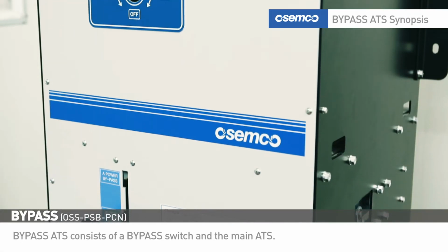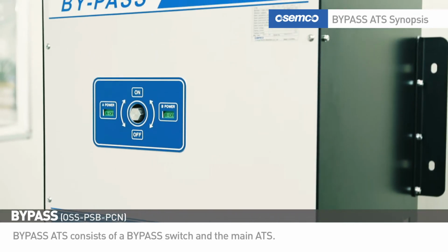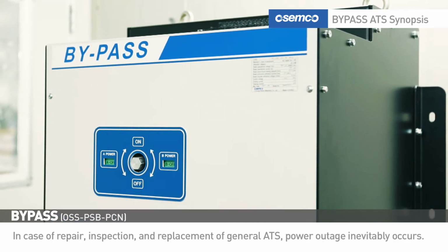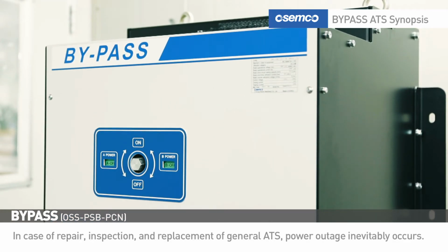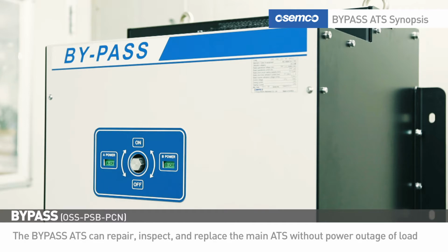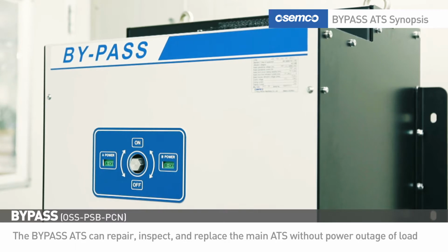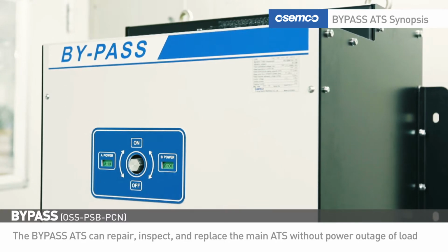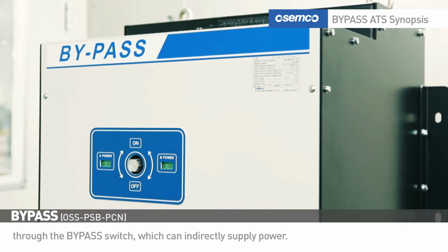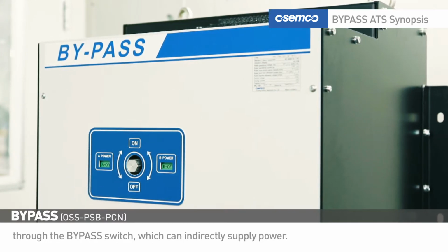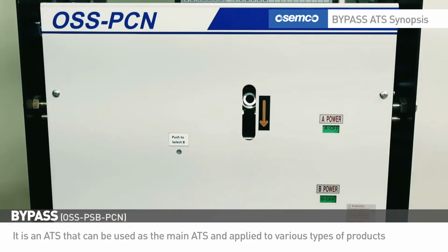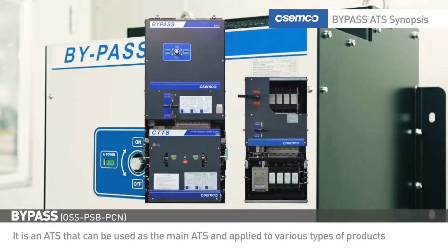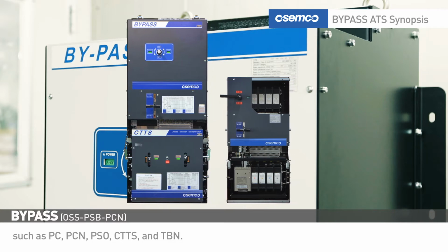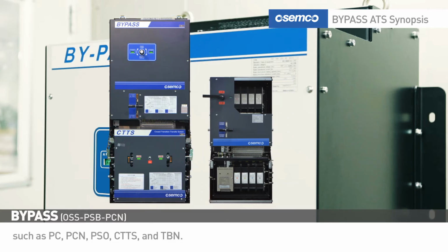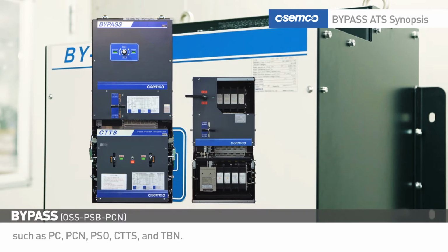Bypass ATS consists of a bypass switch and the main ATS. In case of repair, inspection, and replacement of a general ATS, power outage inevitably occurs. The bypass ATS can repair, inspect, and replace the main ATS without power outage of the load through the bypass switch, which can indirectly supply power. It is an ATS that can be used as the main ATS and applied to various types of products such as PC, PCN, PSO, CTTS, and TBN.